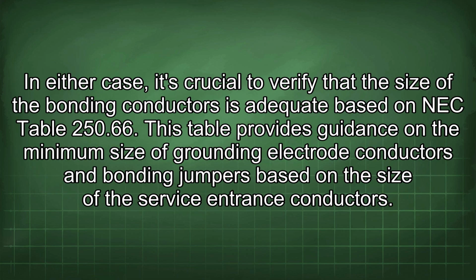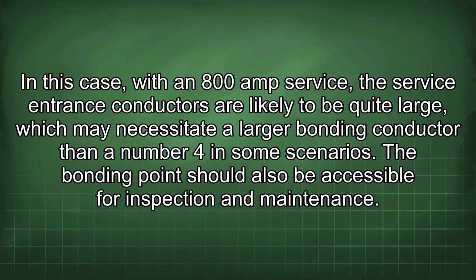In either case, it's crucial to verify that the size of the bonding conductors is adequate based on NEC Table 250.66. This table provides guidance on the minimum size of grounding electrode conductors and bonding jumpers based on the size of the service entrance conductors. In this case, with an 800 amp service, the service entrance conductors are likely to be quite large, which may necessitate a larger bonding conductor than a number 4 in some scenarios.